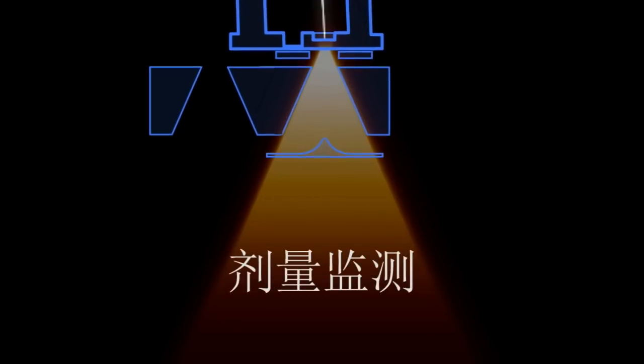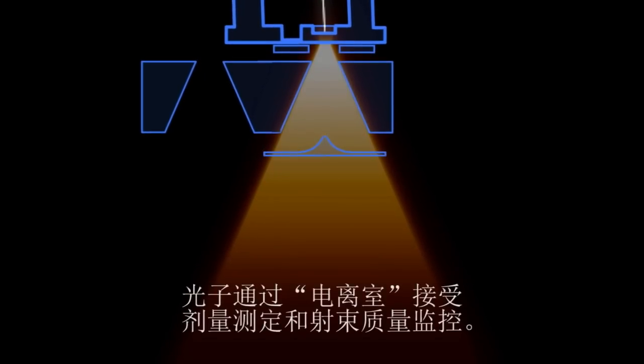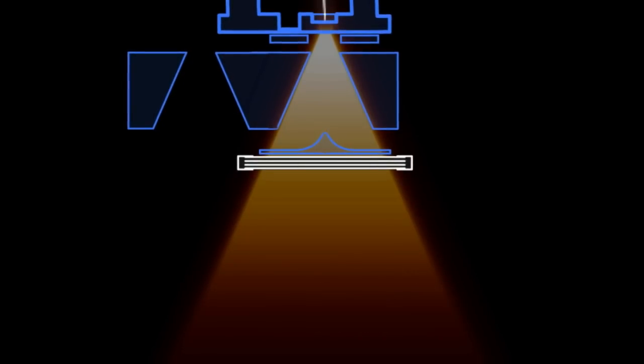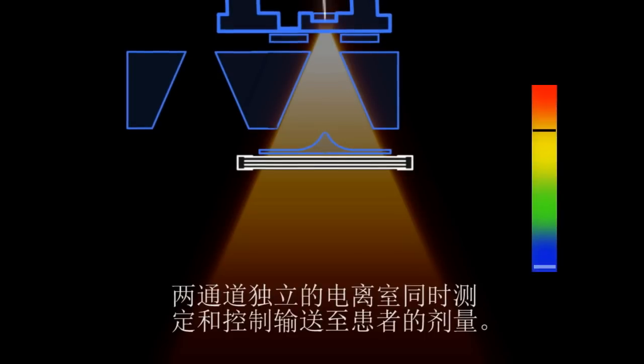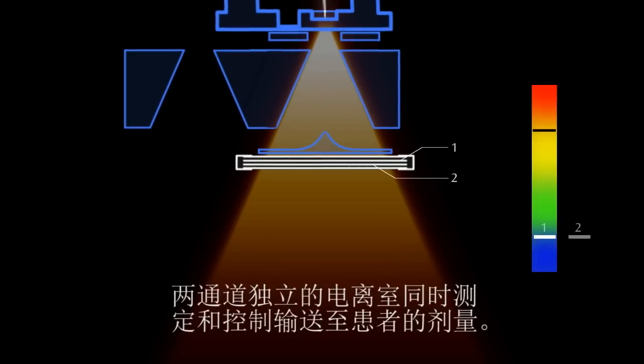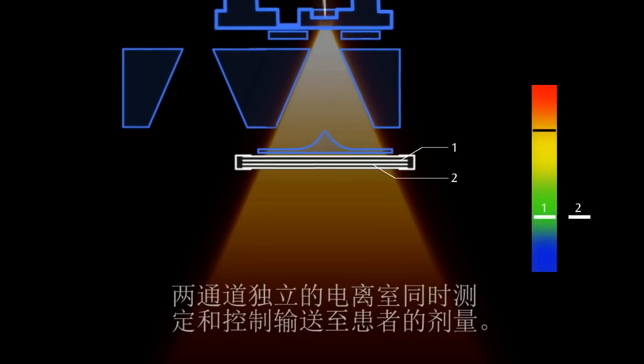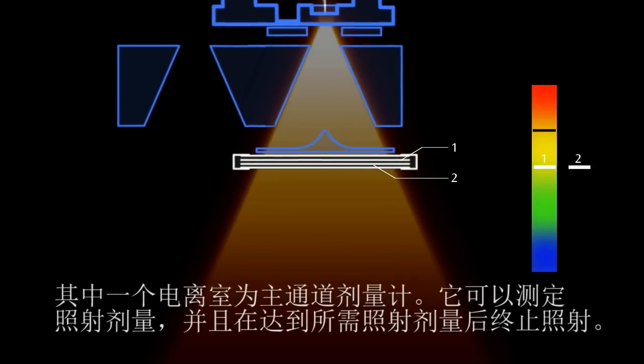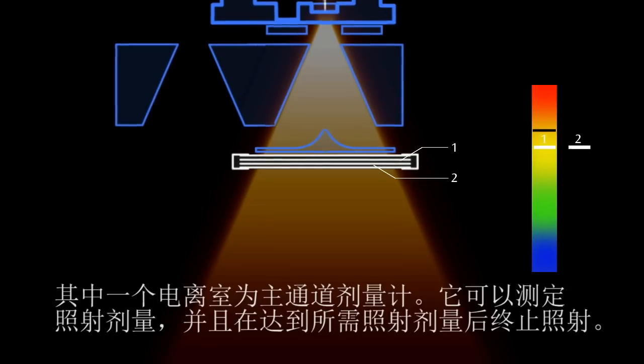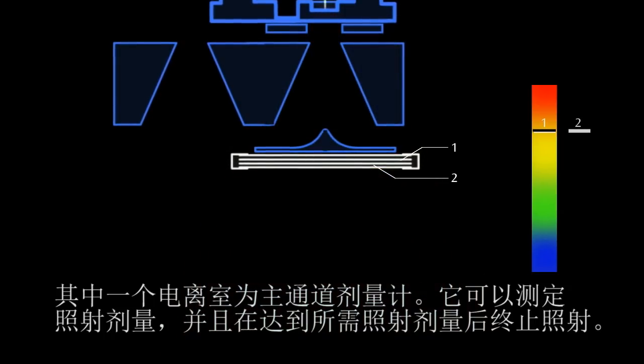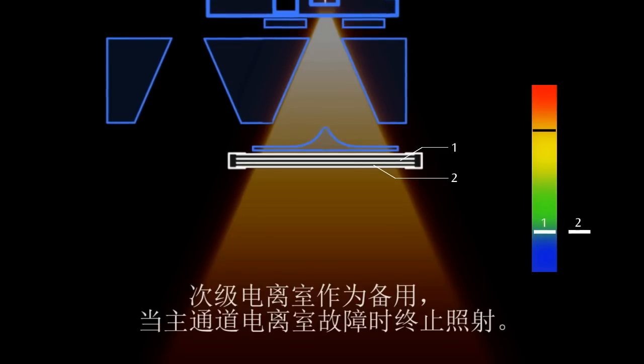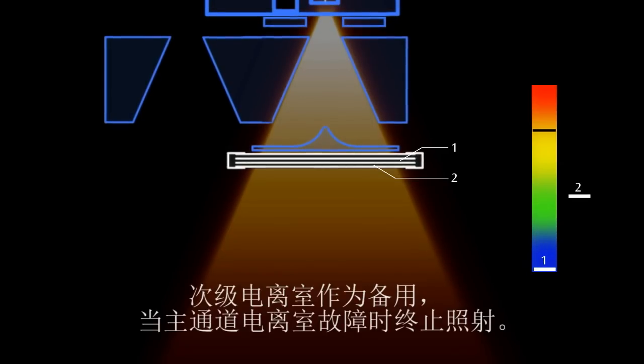Dose measurement. The photons now pass through the ion chamber for dose measuring and beam quality monitoring. The dose delivered to the patient is measured and controlled simultaneously in two independent ionization chambers. One chamber is the primary dosimeter — it measures the radiation and terminates the beam when the required dose has been delivered. The secondary ion chamber acts as a backup and will stop the irradiation if the primary chamber fails.